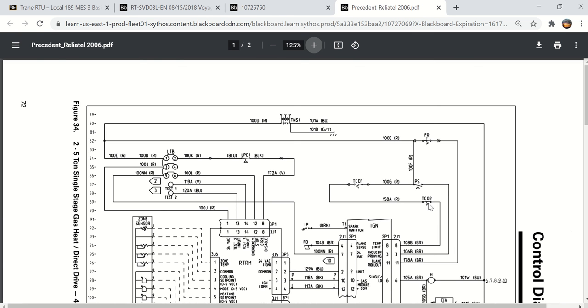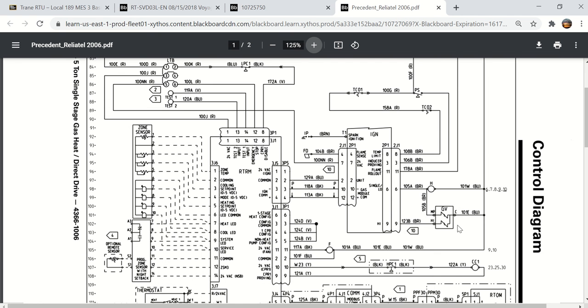One thing I wanted to show you is the difference between this temperature symbol here for TCO2, which is a high limit, and this one, which is the flame rollout temperature. You see how it has the line above with what looks like it could be a button. Well, that's because this is a manual reset. The flame rollout is manual reset. TCO1, TCO2, the high limits, those are automatic reset. Here is the gas valve. This is a two-stage gas valve. There's low and then high.